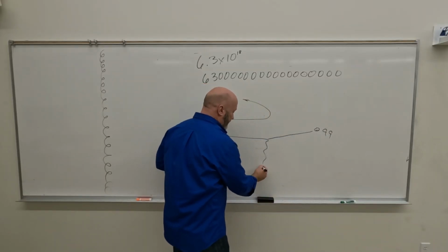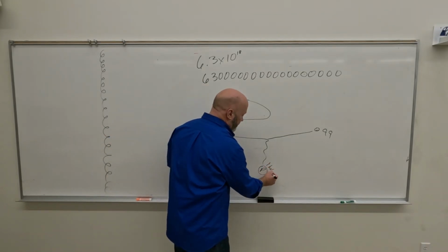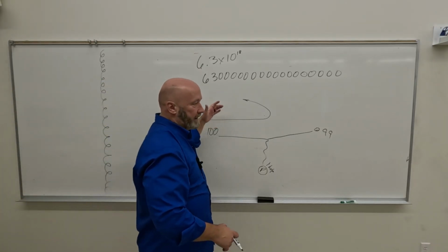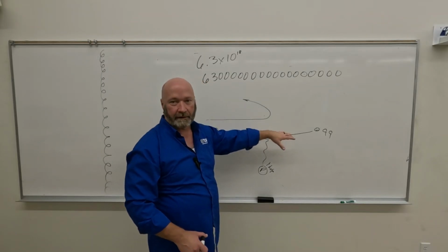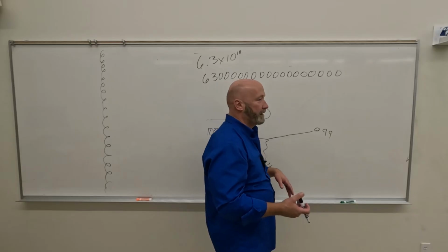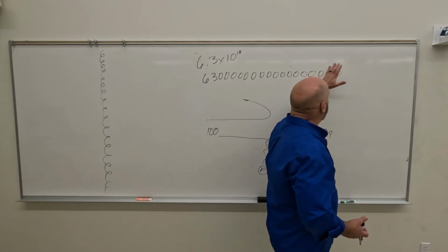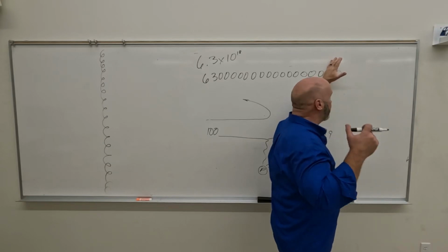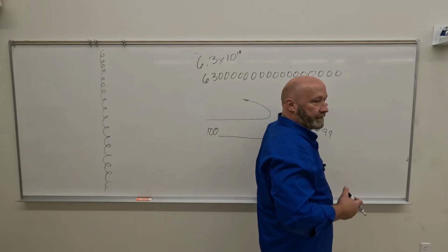Did we get an X-ray photon? Yeah. And what's the energy of it? 1 keV, right? So what we say is that the electrons travel across the tube. Most of them just complete the circuit, don't create X-rays. Depending on the kVp level that we're using, we say maybe 99% creates heat. Or saying it the other way, only 1% of all of those on 1 amp exposure would become X-rays.